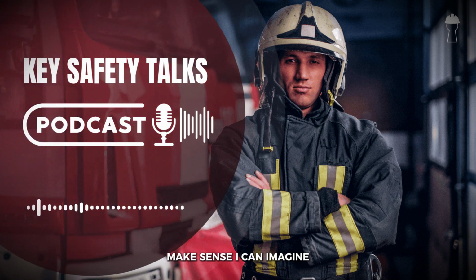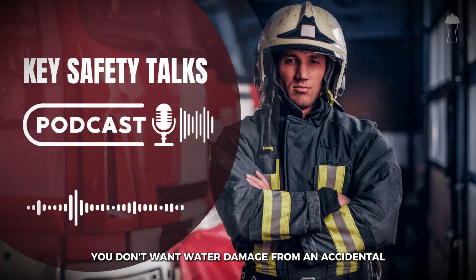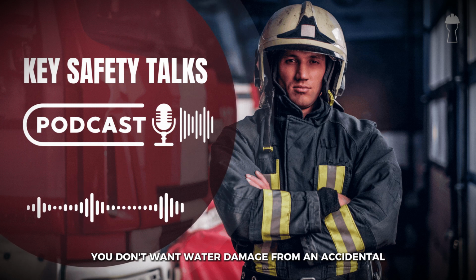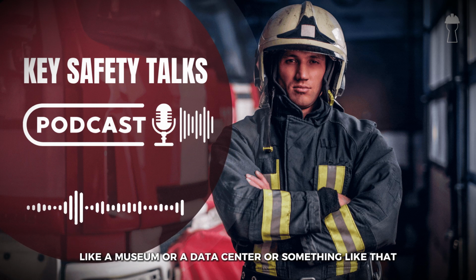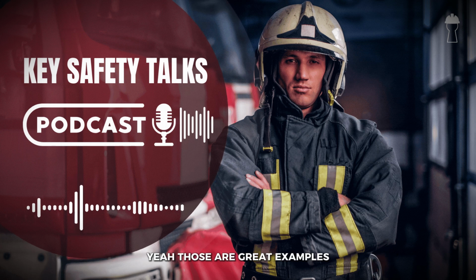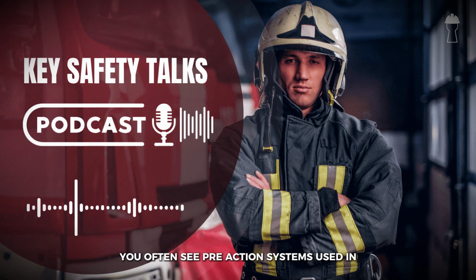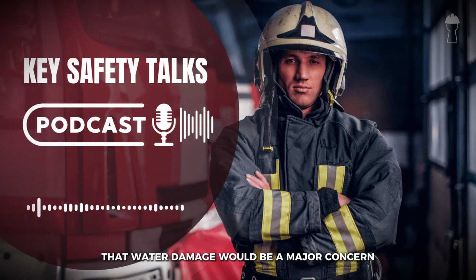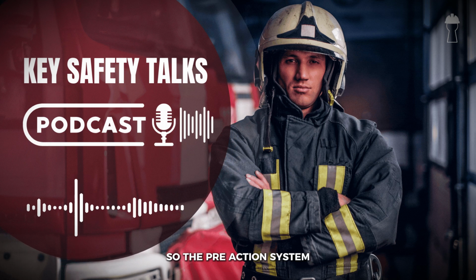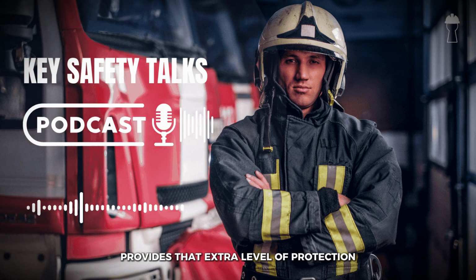Makes sense. I can imagine there are certain situations where you don't want water damage from an accidental sprinkler discharge, like a museum or a data center or something like that. Yeah, those are great examples. You often see pre-action systems used in places where that water damage would be a major concern. Right. Okay, so the pre-action system provides that extra level of protection.